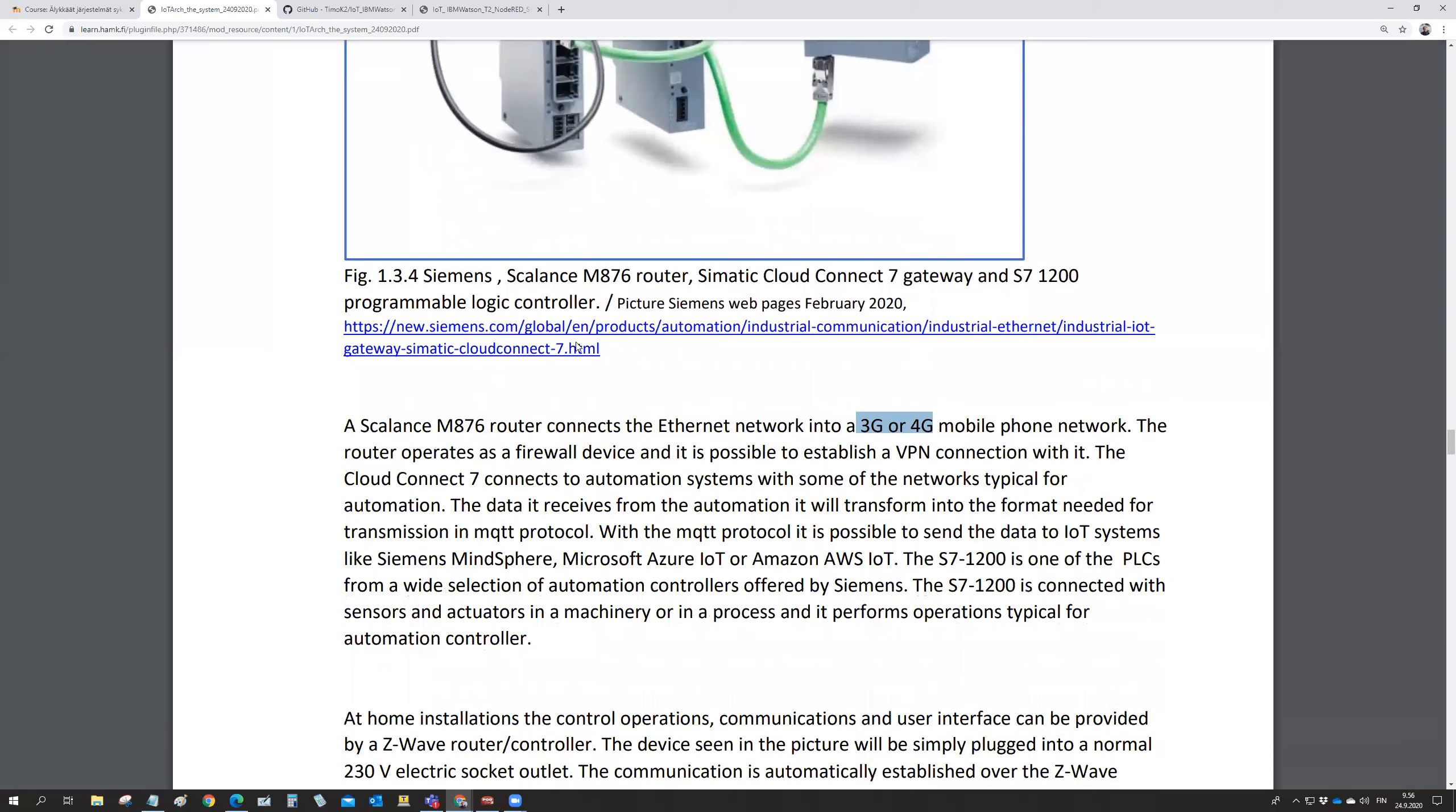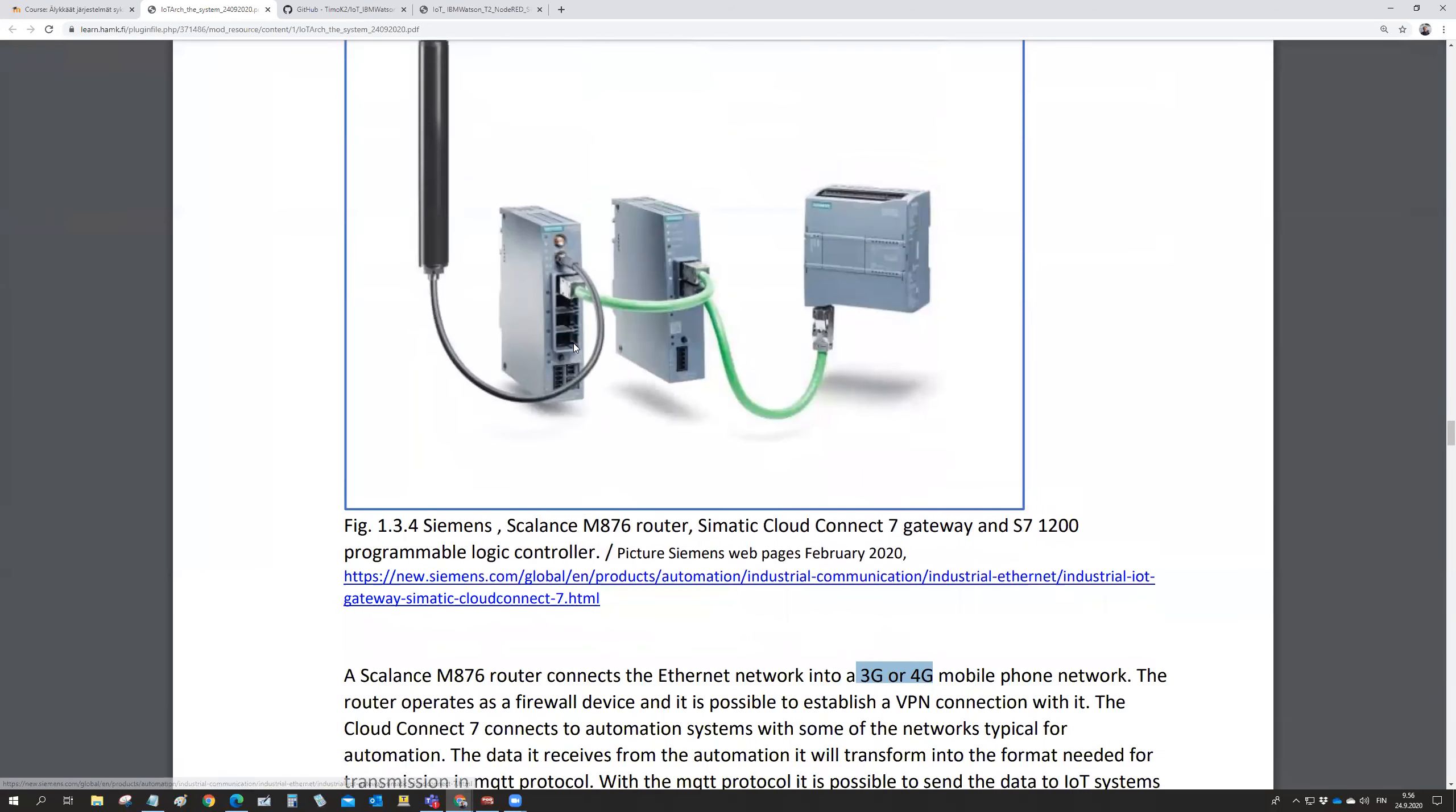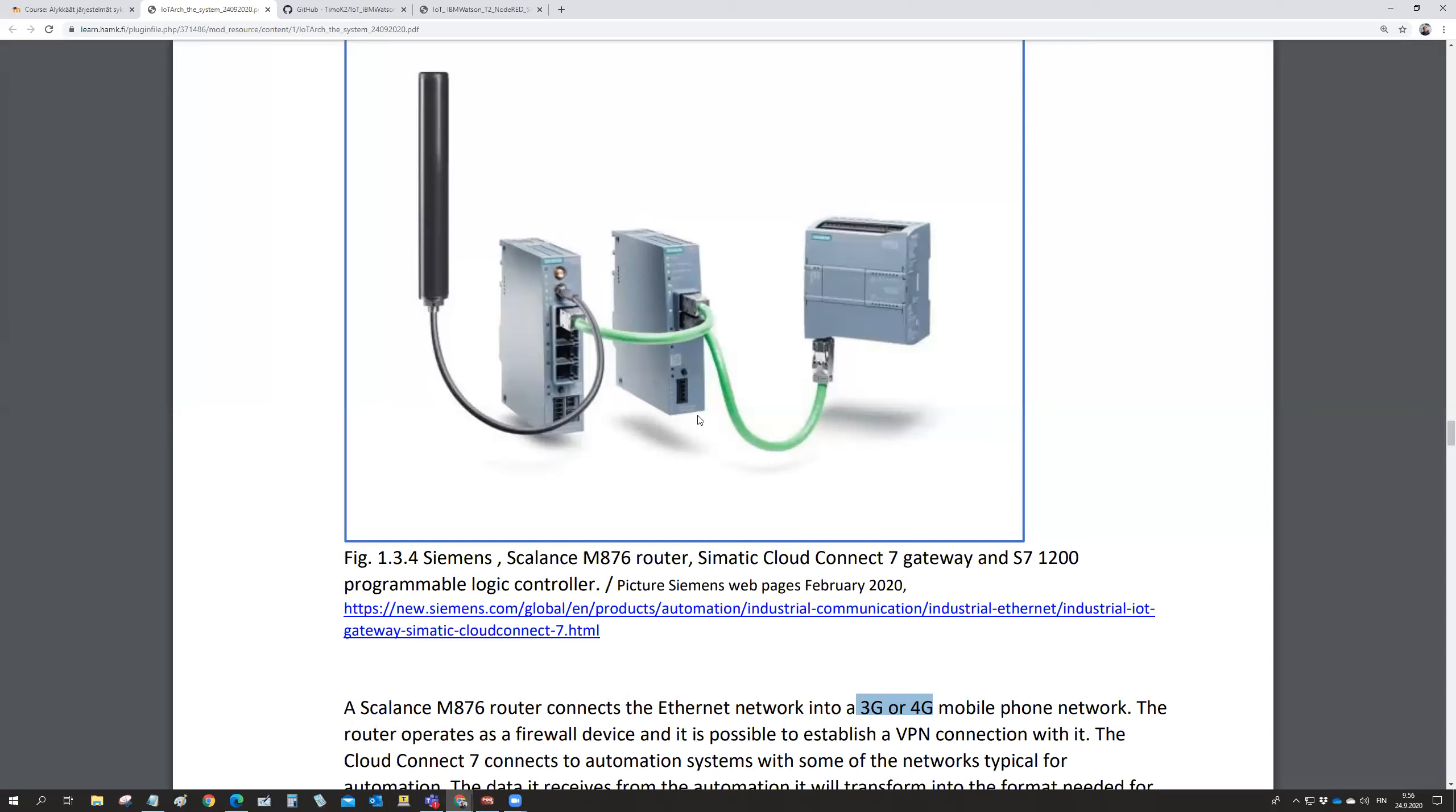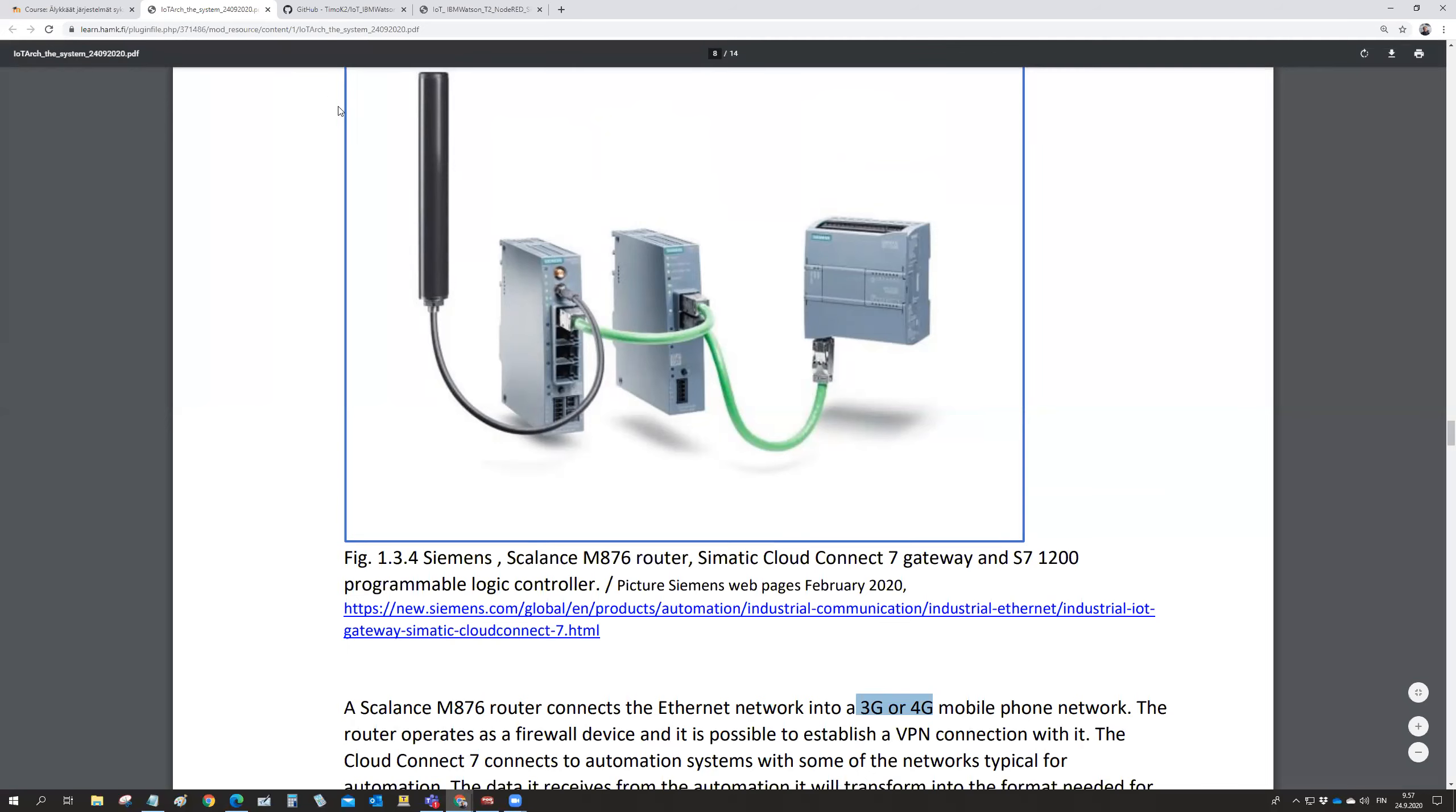The box in the middle is the Cloud Connect gateway, which is getting information from the memory of this controller and writing that information in a format which is understandable in the IoT system. That's typically an MQTT formatted message, which goes to the router and over the 3G, 4G network to the internet.